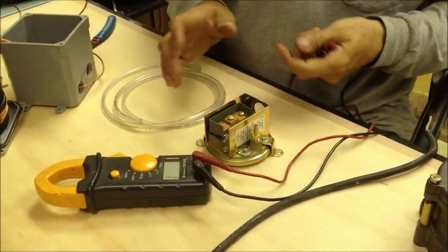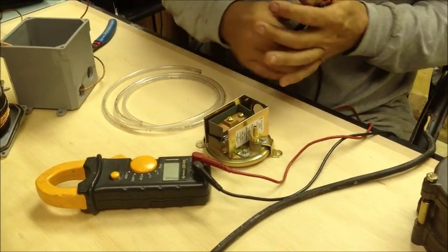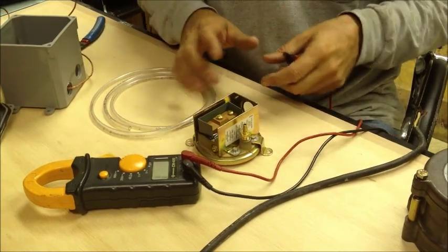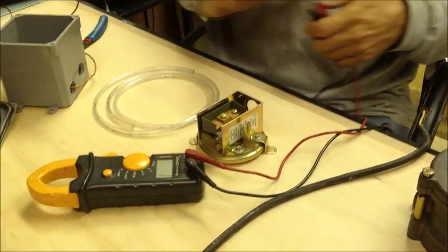What I like to do is just go through what we just did though, test all functions of this switch and make sure it's working. But it is important to know whether it's a vacuum switch or pressure switch, normally open, normally closed.